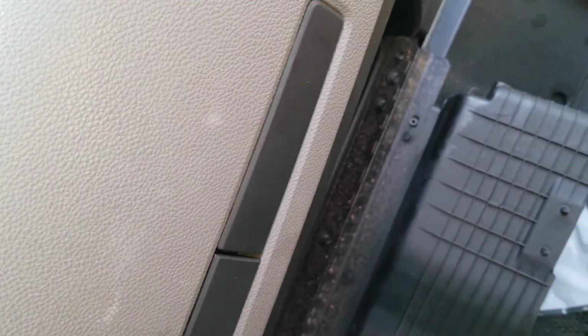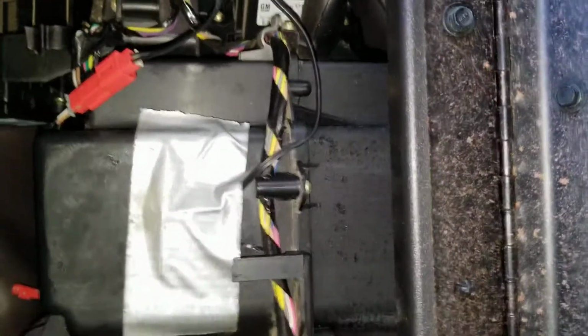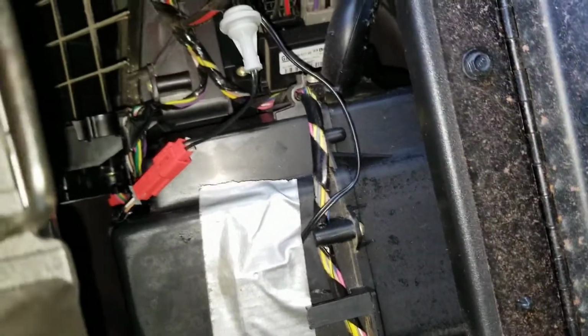So you have a sensor, let's see if I can show it, up above the black box that drops down into the center, and it tells the AC unit how much Freon to push through. When it fails, it tells the system it's like 150 or 175 degrees, depending on which one it is. So the system runs too much, and everything inside that box freezes over and you get no airflow.